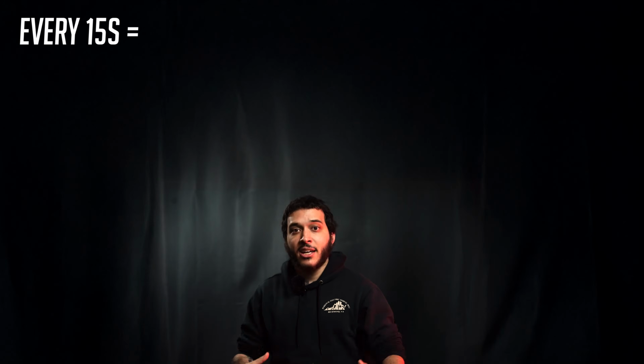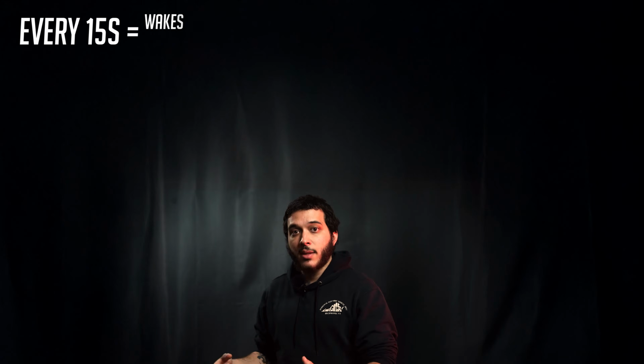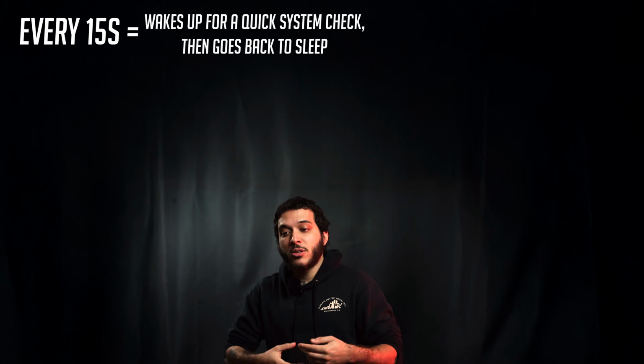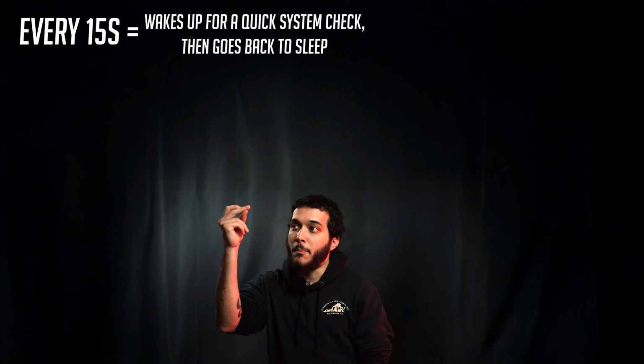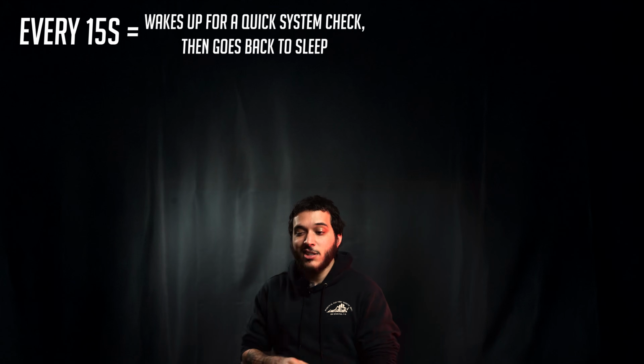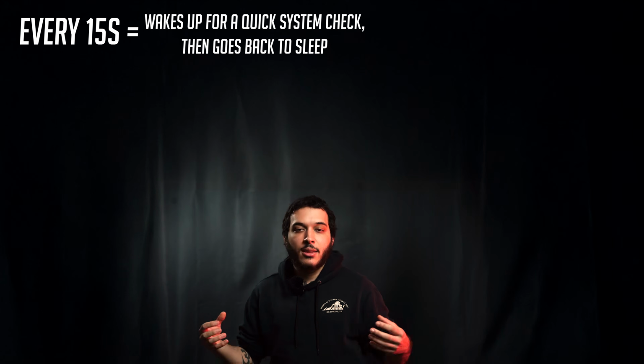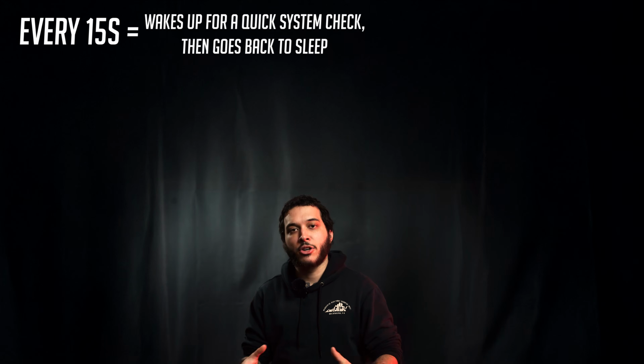Once you receive your VBMS unit, you're going to notice that it's very vocal. There's a double beep that'll happen seemingly randomly. And if you look, you'll notice that there's no toggle switch for this beeper. I told you I'd come back to this later. Essentially what is happening is that every 15 seconds, the VBMS is going to turn on to do some light system checks, and then will immediately turn back off. This is happening all the time so that the BMS can consistently monitor itself.